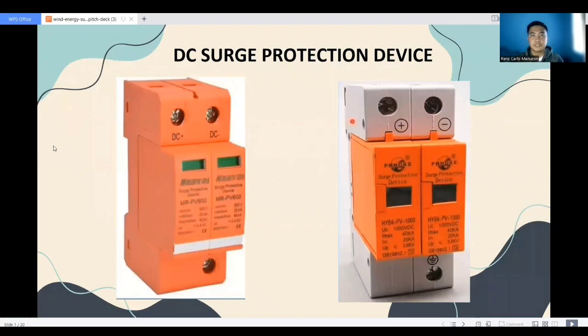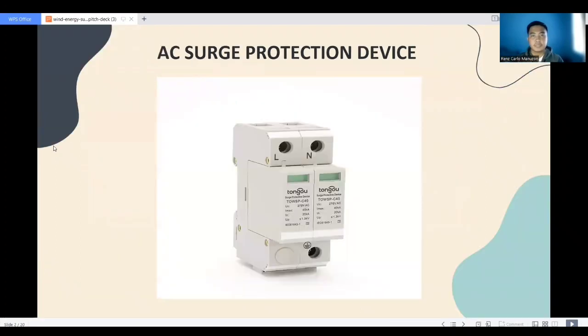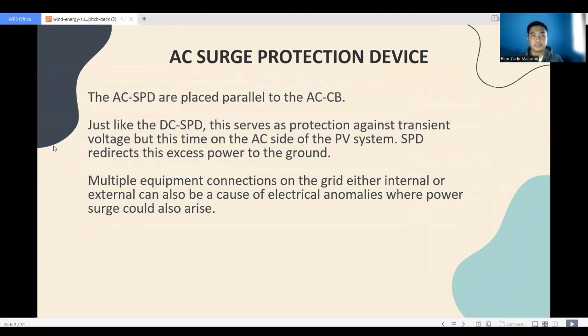The DC protection device and the AC protection device. The AC SPD are placed parallel to the AC CB. Just like the DC SPD, this serves as protection against transient voltage, but this time on the AC side of the PV system. The SPD redirects this excess power to the ground.